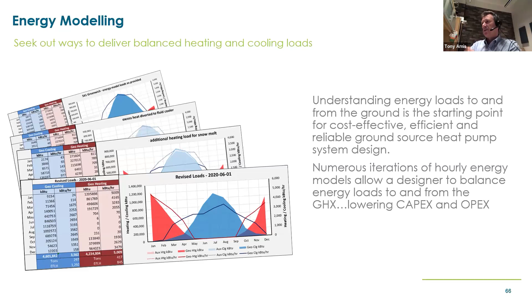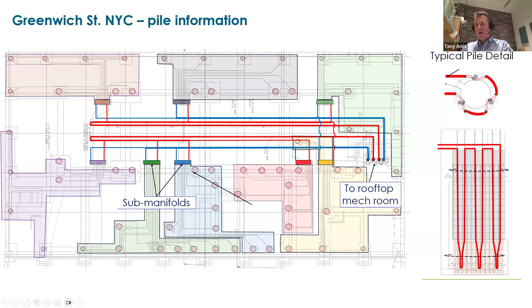But on this Greenwich project, we had 63 120-foot deep piles, 26 and 32-inch caissons, large enough for us to put three geothermal loops into each pile. The loops in each of the piles were connected in series and run back to seven or eight manifolds that you see here. Each manifold is then run back to a main manifold where it all runs up to the roof and delivers the fluid to the heat pumps.